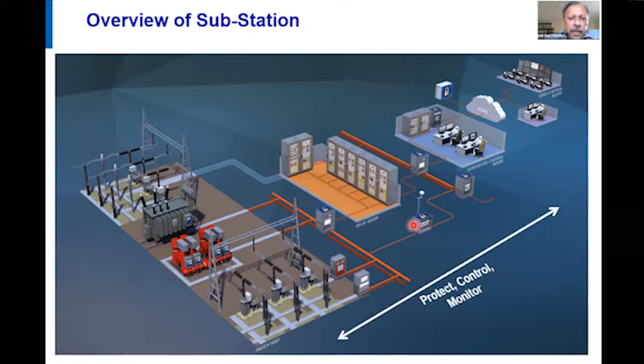Today, with the digital substation, the need for relay rooms is getting eliminated. More bay control units are coming in, and copper cables are being reduced by optical fibers coming out from the switchyard, connected to various engineering and operator workstations, and also to the remote load dispatch center. This means you can have no manpower at the substation.